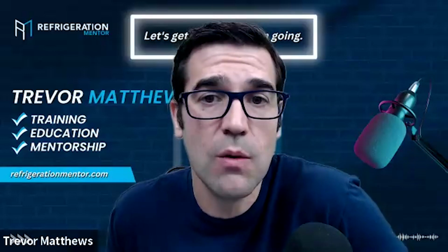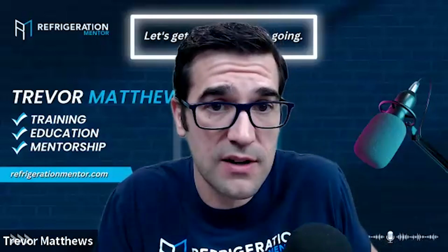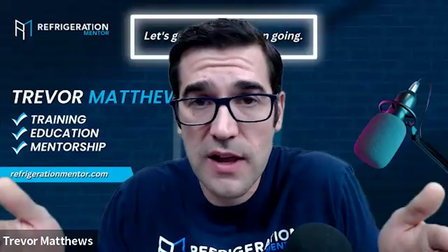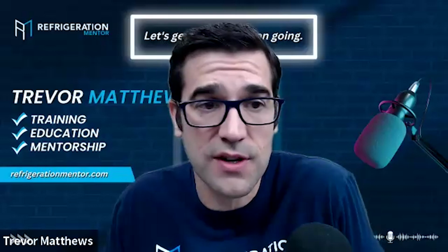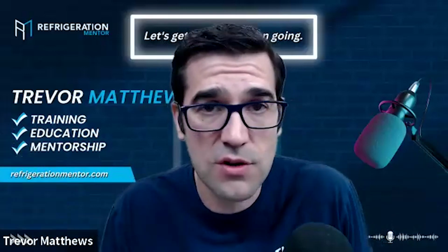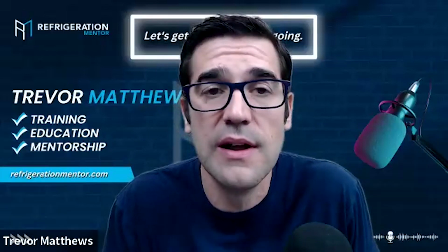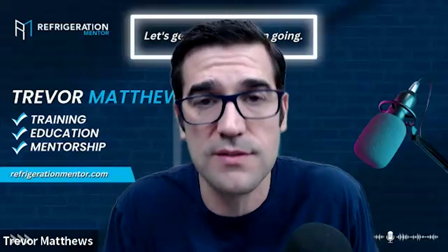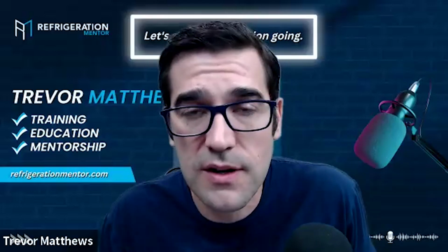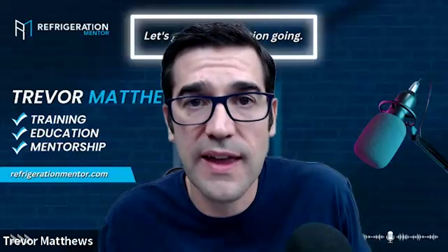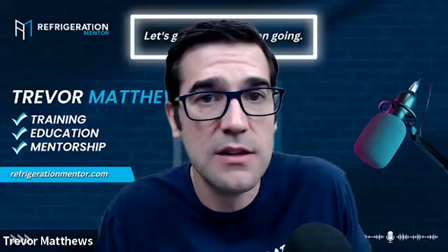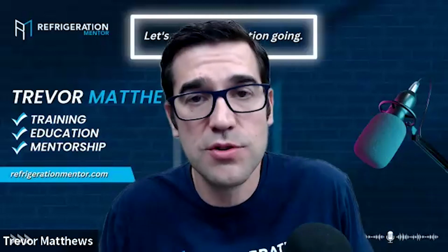So you need the wiring diagram, because you can call Rusty up and say, listen, I have this circuit here - it's the control circuit, or the compressor circuit, or the condenser circuit. Here's my points, here's the voltage going down, there's this transformer here, I'm not reading the right volts. It could be like someone just added another controller on it and you don't have enough VA to open the electronic valve or not.